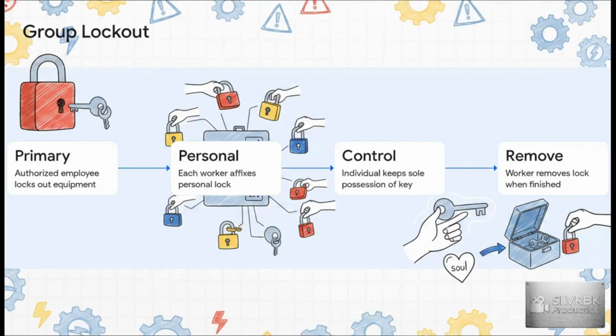We see this concept play out most clearly in group lockout scenarios. Even if a primary authorized employee locks out the main energy source, or maybe a shop lock is employed to lock a box with multiple keys inside it, or a multi-lock hasp is used, it doesn't matter. Every single individual working on that equipment must walk up and affix their own personal lock to each lockout point, or onto that gang box. They have to keep the key in their sole, and I mean SOLE, possession, and they're the only ones who can remove their personal lock when their portion of the work is finished.